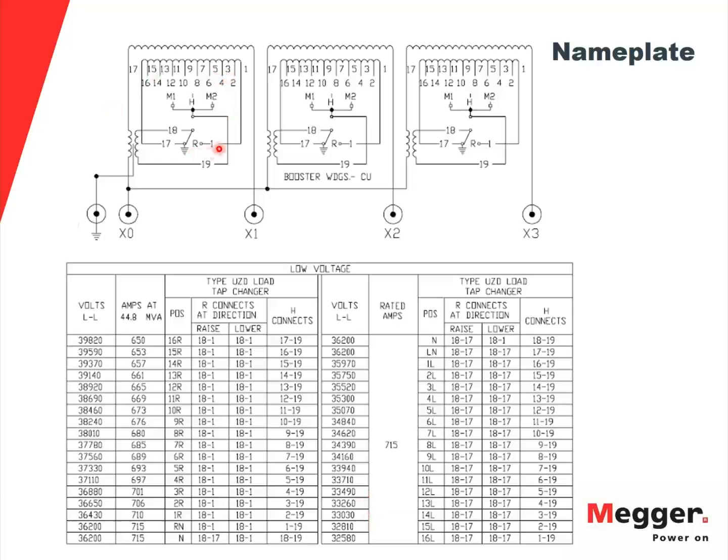With the 16 tap positions and the reversing switch, I can obtain 33 tap positions. And those are the 33 tap positions you see on the nameplate.